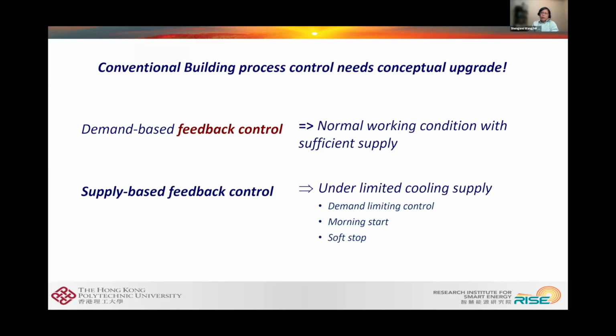So actually, in buildings, there are typically 3 cases where we have this problem of limited cooling supply. One is demand limiting control, as I mentioned. Another is the morning start. In the morning start period, particularly in hot areas, such as Hong Kong and I think parts of the States, in the summertime, or such as in Hong Kong, where we have half a year of it, the system is rather hot at the starting period, a high temperature start. So even if we start many chillers, the cooling supply is not yet sufficient. The morning start period actually faces a situation where the cooling supply is not enough.